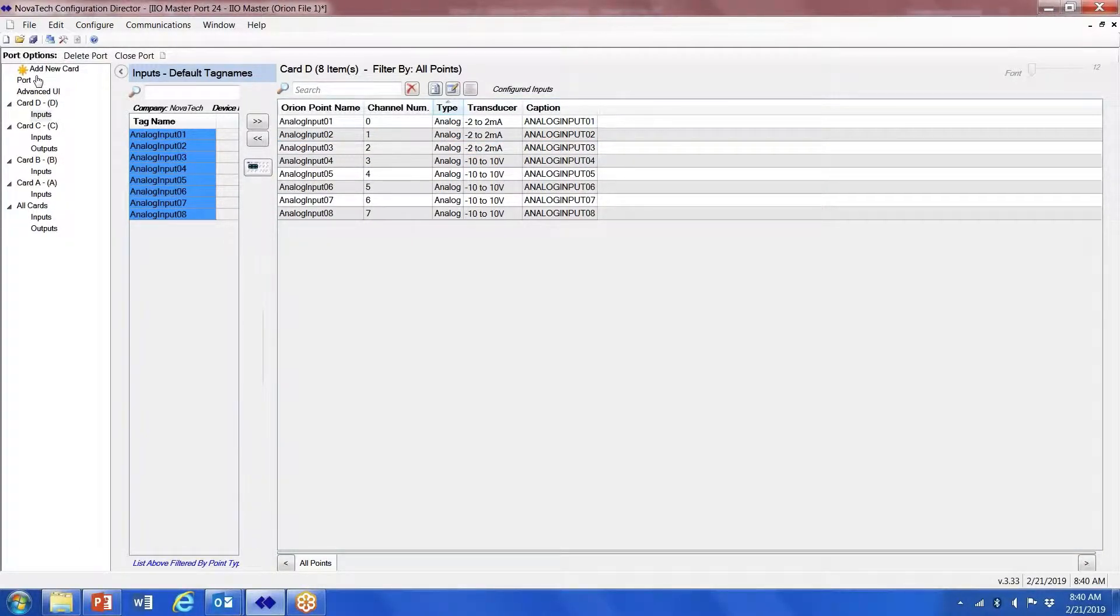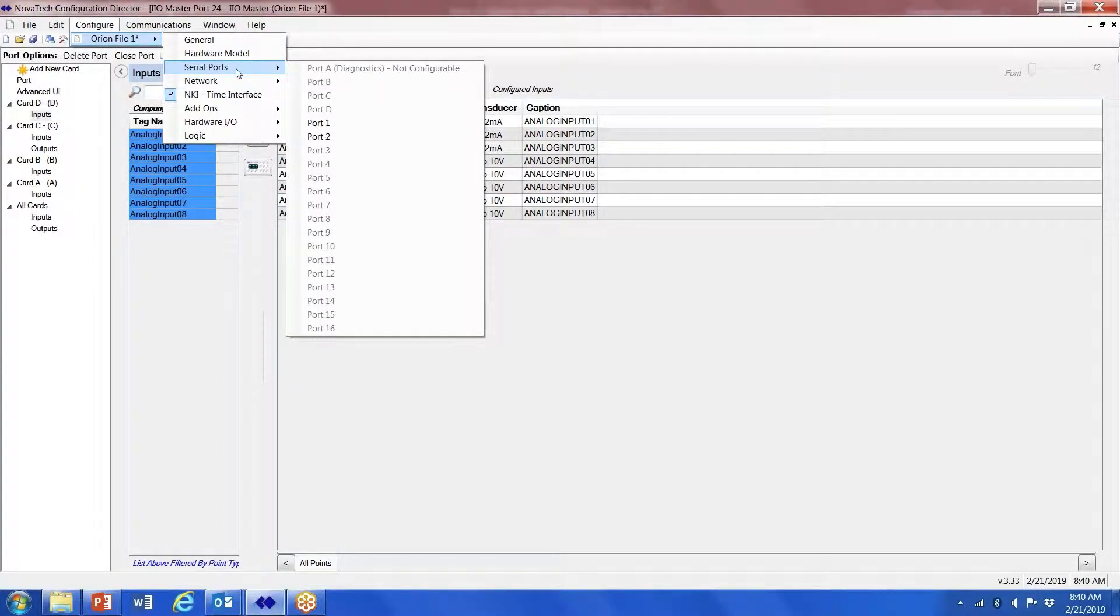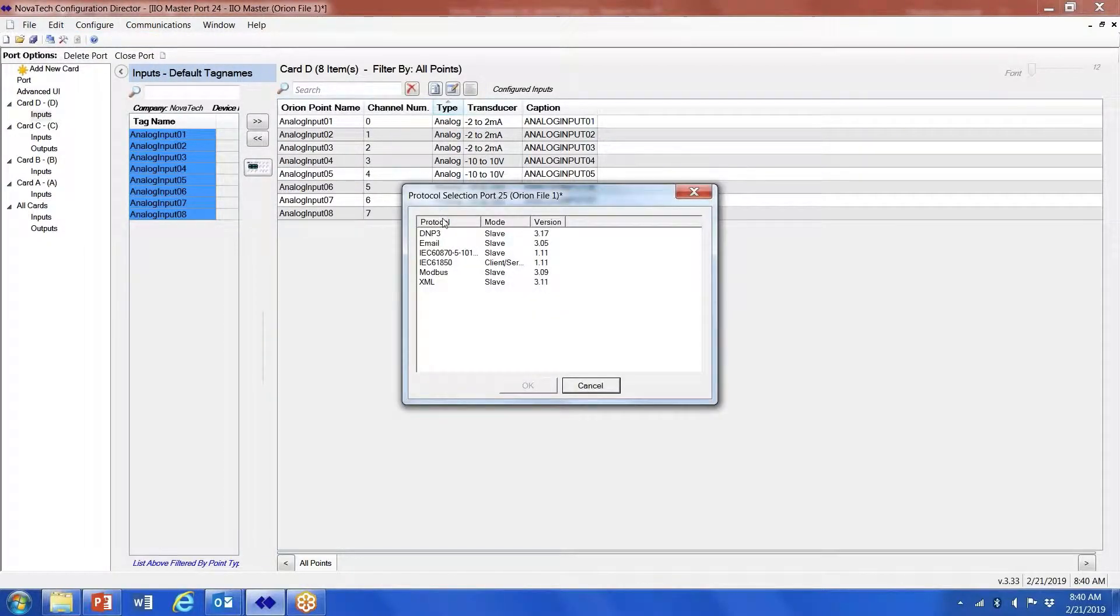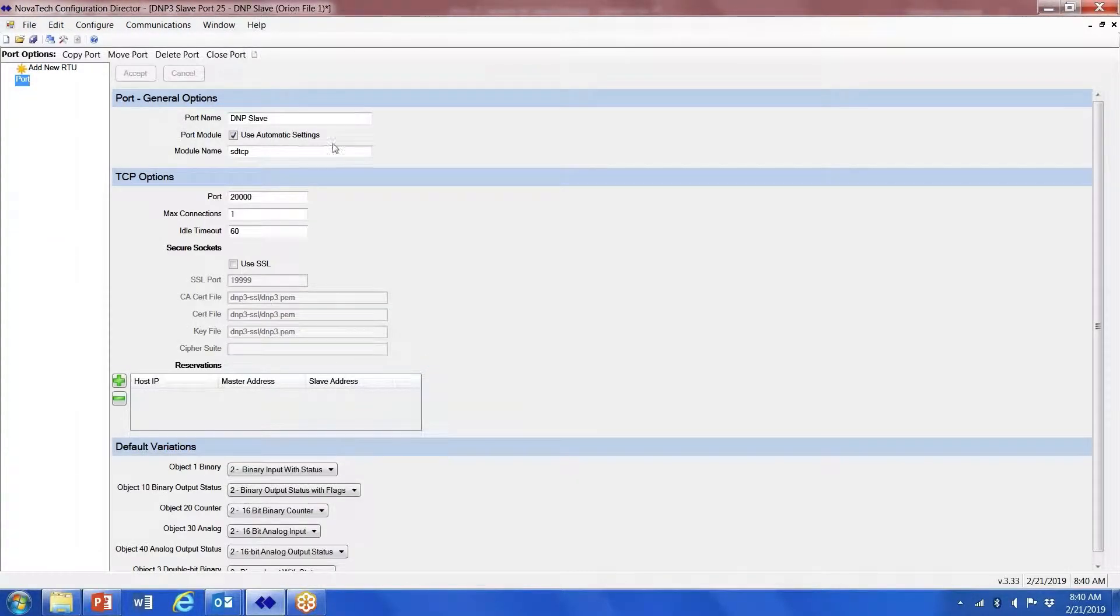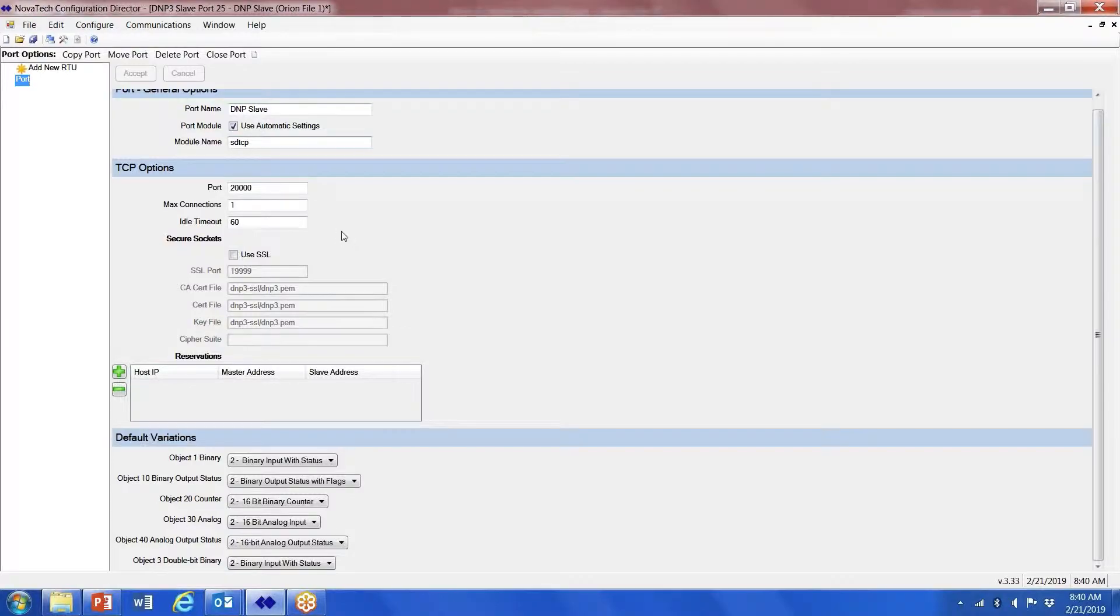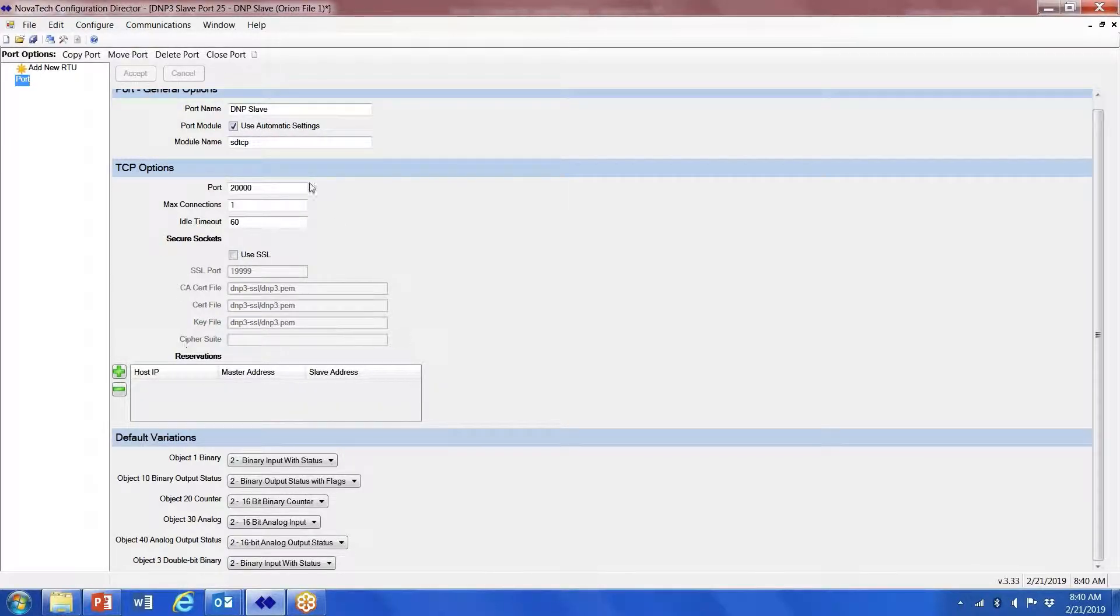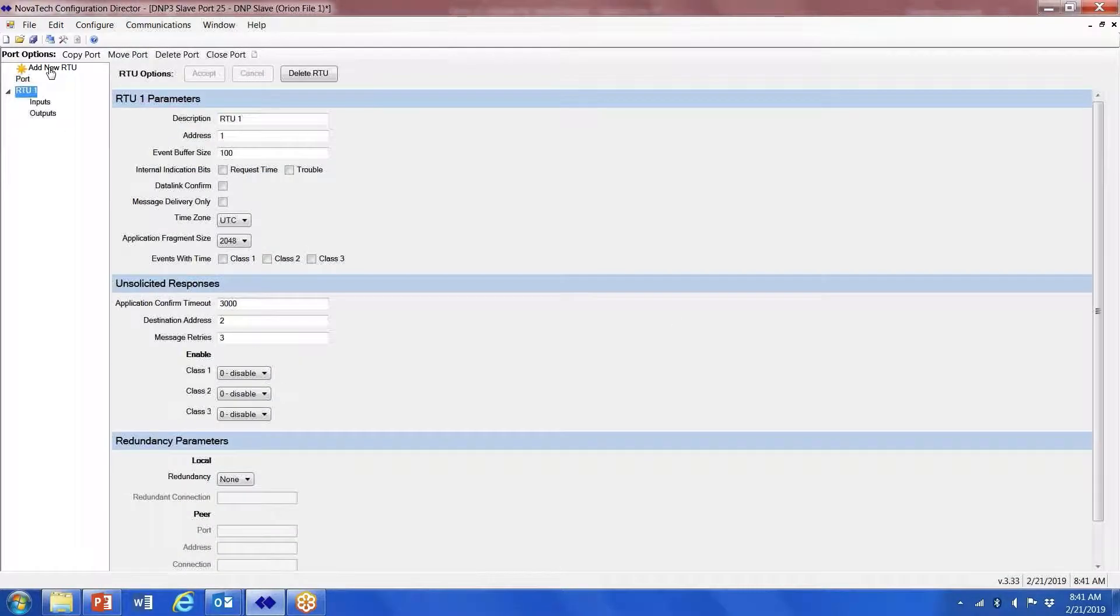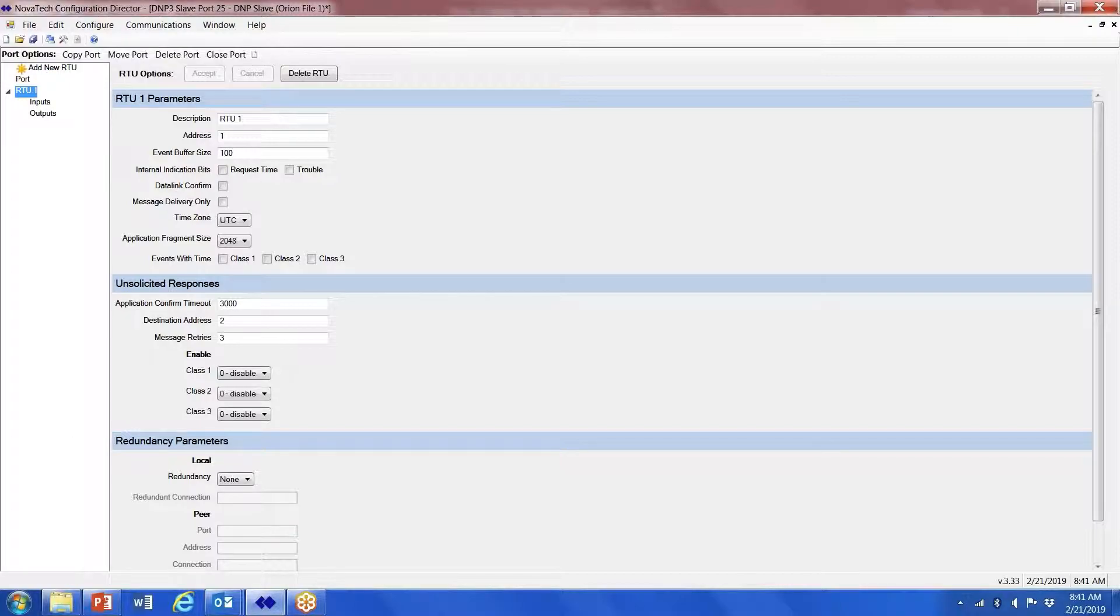Once I'm done there, then I go back to configure Orion file. Now I'm either going to use a serial port or a network port to set up my DNP slave point. I'm just going to go in and define what my ports are, my typical DNP slave information, default variations, etc.